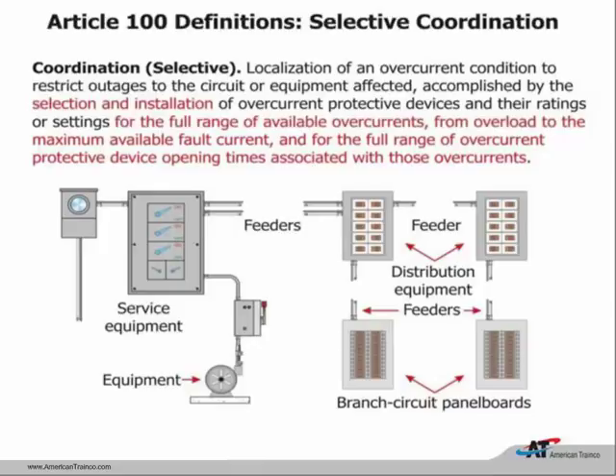In definitions, the technical committee has been working on selective coordination for about three code cycles. Selective coordination means the overcurrent device closest to the fault is the one that operates first. In red, they have introduced new wording: it's going to be for the full range of available overcurrents, from overload to the maximum available fault current. That's going to present a challenge, because it was difficult enough to coordinate those overcurrent devices when talking about just fault current—now we're talking about overloads also.